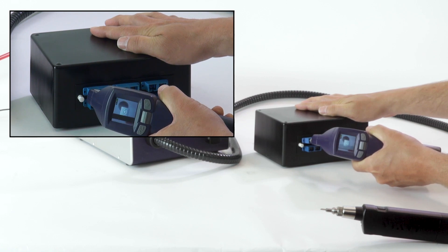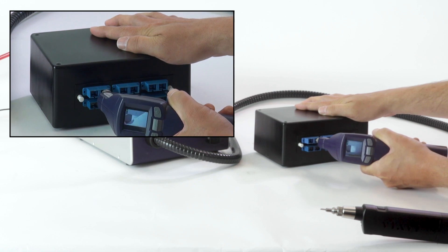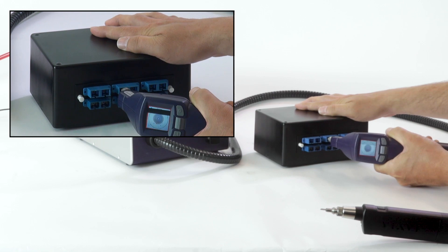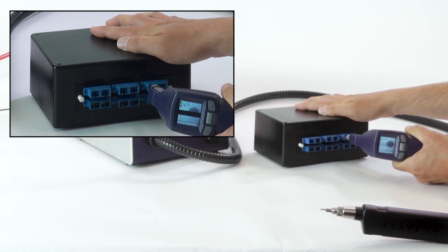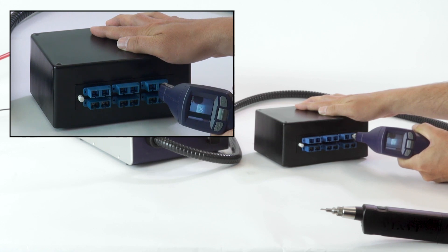I'll use the fiber check probe — I can see that one's dirty. That's dirty. I'm going to go ahead and check all six of these. That one's dirty. That one's dirty. That one's really dirty. And this one looks pretty dirty as well — sure enough, it is.